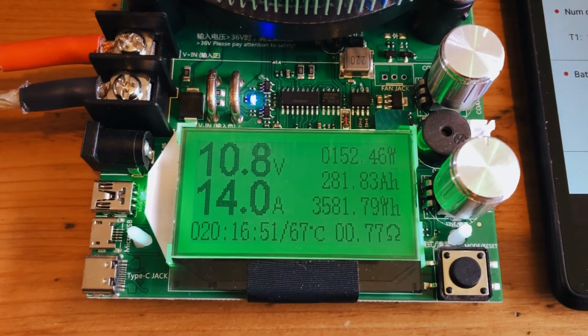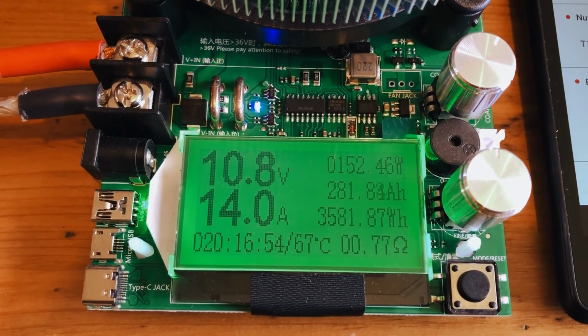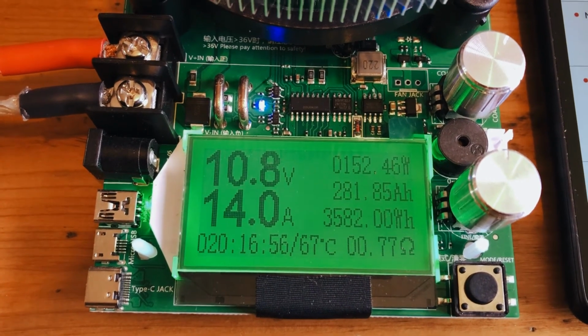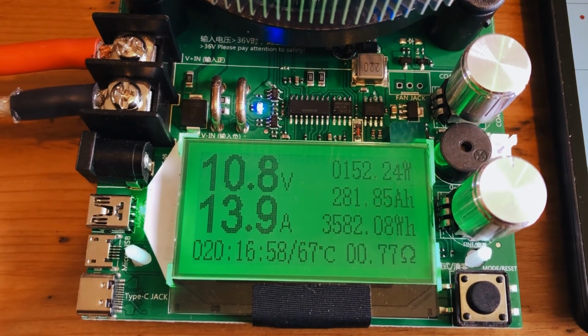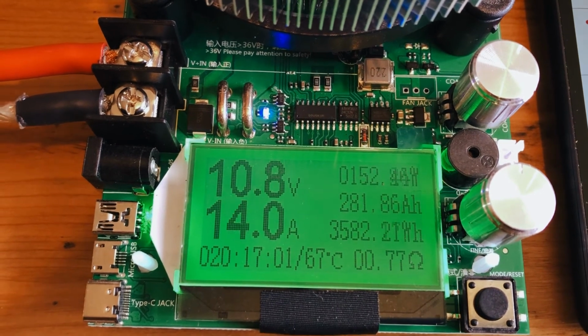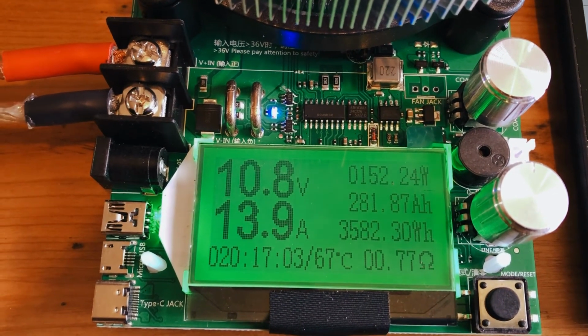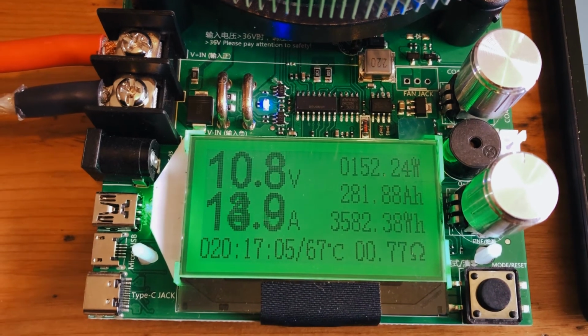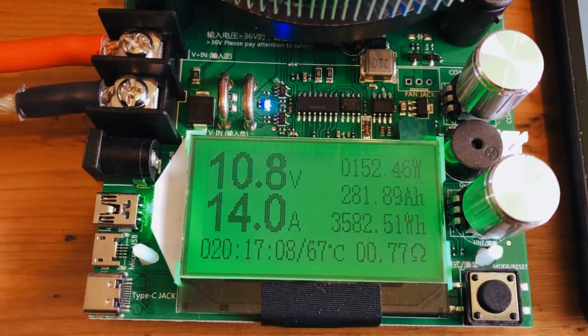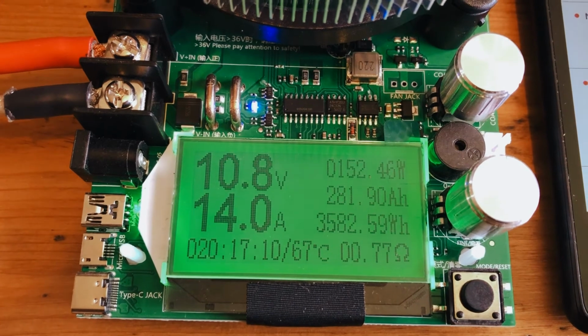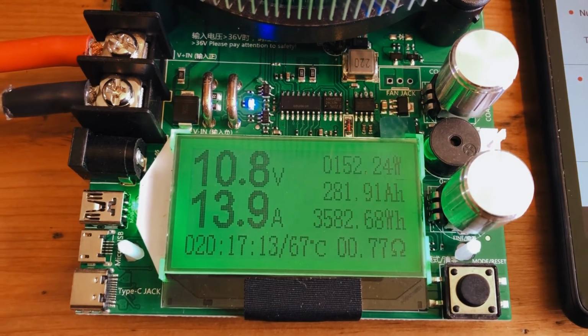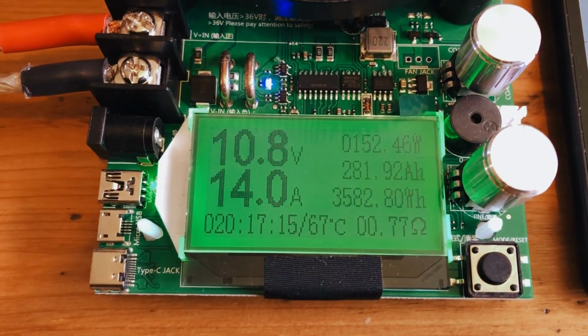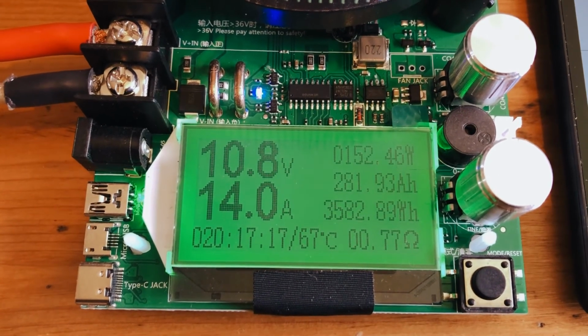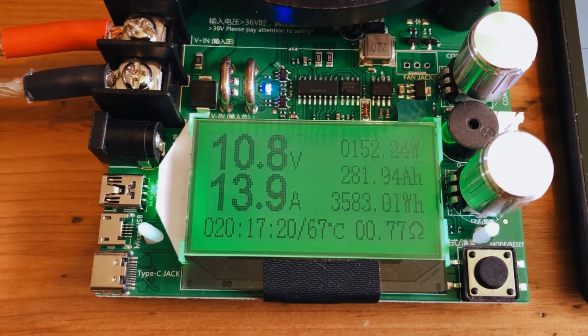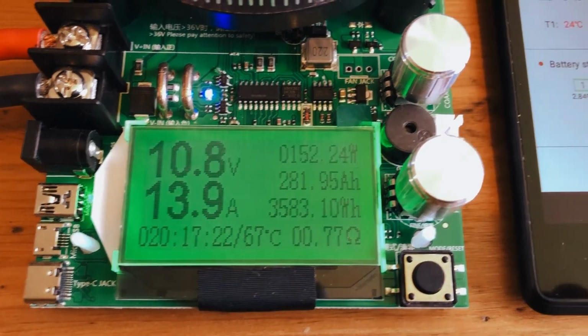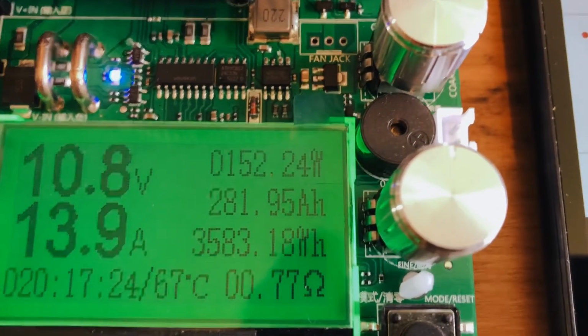So according to the inverter, if we were running it, measuring through a shunt, we would have reached probably, well, the last time we ran this test, we would have reached about 277, 78, just because the high current draw drops that voltage quite quickly. And as I said, the inverter cuts off at 11 volts.